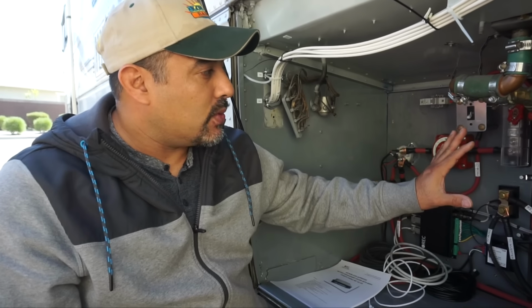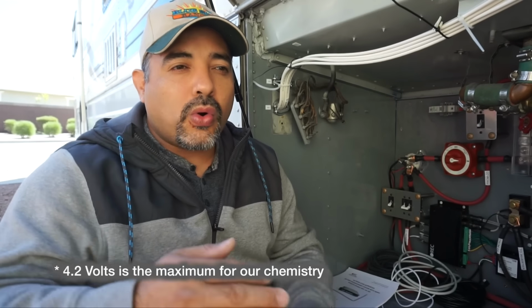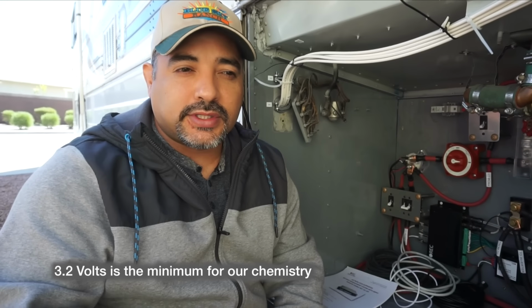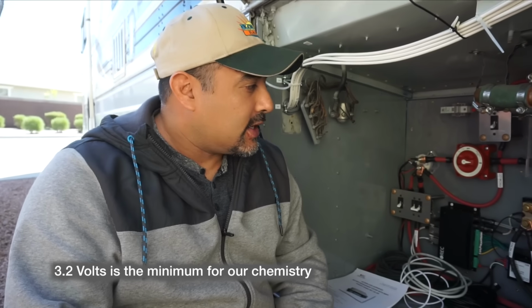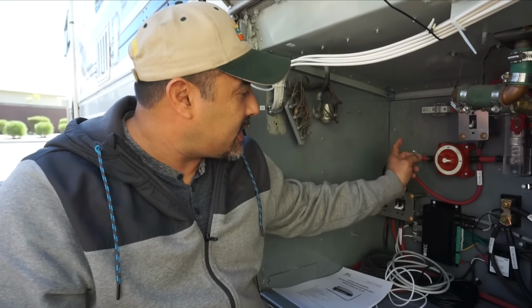The purpose of a BMS, which stands for Battery Management System, is to monitor the battery and be sure it remains within its specifications. That includes voltages. For lithium batteries, everyone's heard of lithium fires, cell phones catching fire, and things like that. That happens if lithium batteries get overcharged, meaning over 4.2 volts, or undercharged, under 3.2 volts, which risks damaging the cells. So this ensures that if it ever gets outside those parameters, it shuts everything off and sounds an alarm.